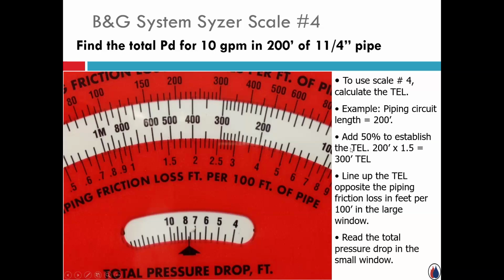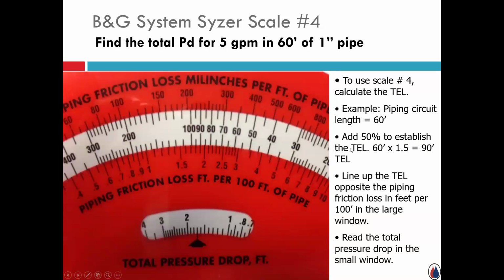And all you do on that scale 4 is you find the 300 feet, and you line it up opposite the pressure drop that we established, which in this case, for 1.25 inches, was just about 2.6, I think, per 100 feet. Then line it up opposite 300 feet as my total. Read straight down in this small window where it says total pressure drop. And it's just over 7.5, just under 8 feet. Again, it's just math. It's a convenient calculator, not needed nowadays the way it was years ago.